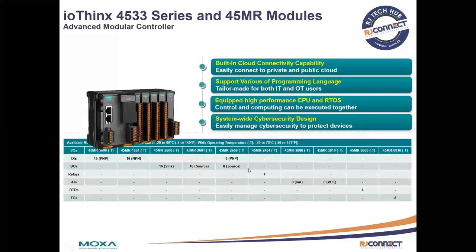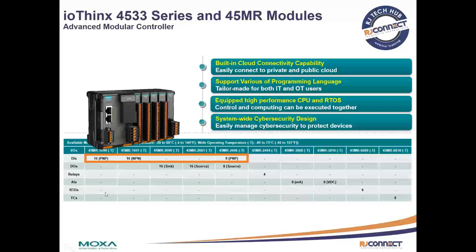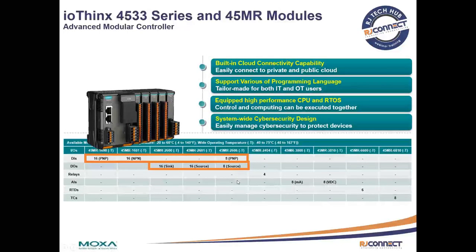And the 45MR modules here, you'll notice that for digital input, we got the 16 channel as well as the 8 channel. And on the 16 channel, we got PNP and NPN. And then on the 8 channel, we only have the PNP. And for the digital output, same applies. We have got 16 channel, which is sink, and then the 16 channel, which can be source. And then on the 8 channel, you have only source.